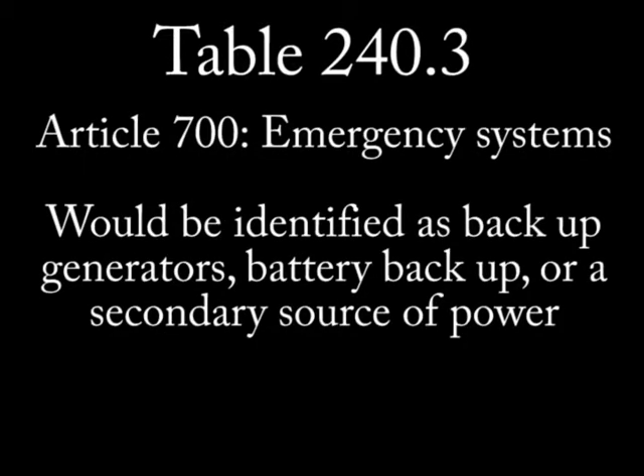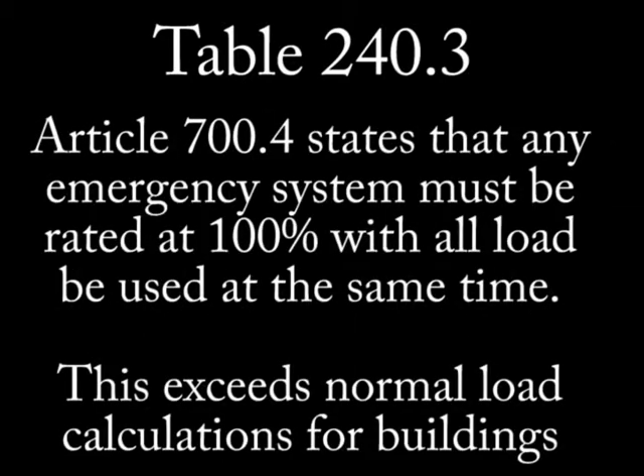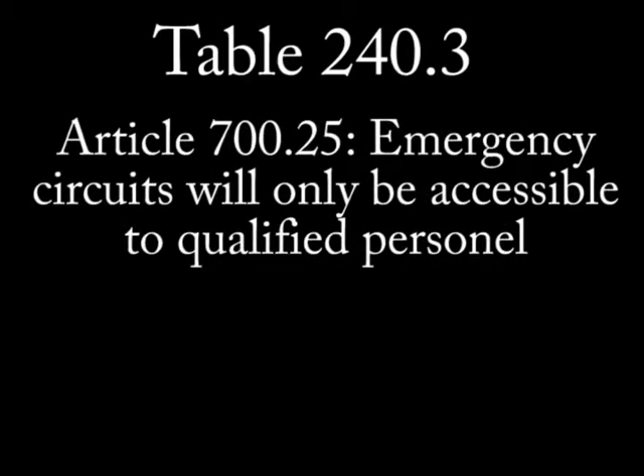Next, we look at emergency systems covered in article 700. I only found two items related to overcurrent protection in this section. First is article 700.4, which means that emergency systems will be rated at 100% so that all loads can be operated at the same time. In most cases, this would mean that the emergency system would exceed the capacity of the original service. Article 700.25 means that the overcurrent devices in the emergency circuits will be accessible to authorized persons only.